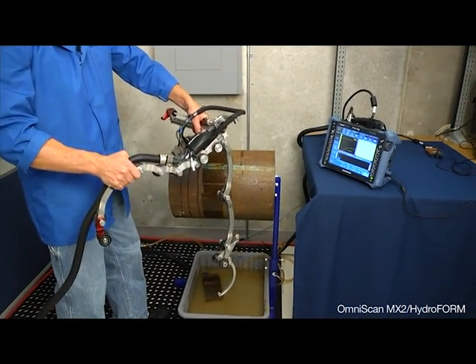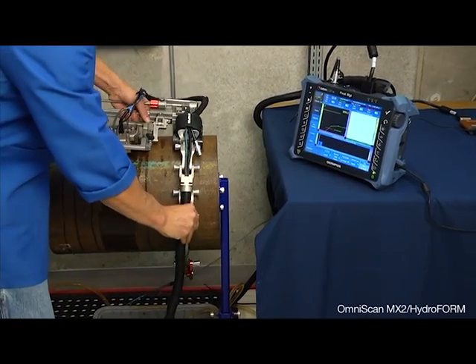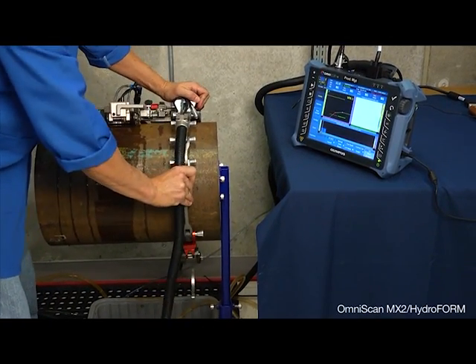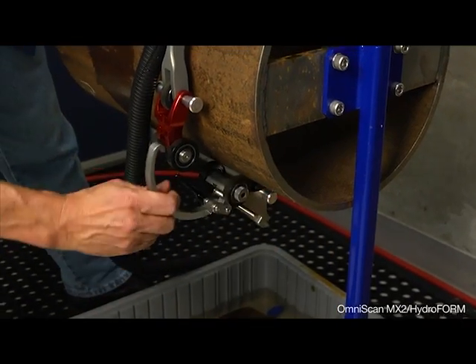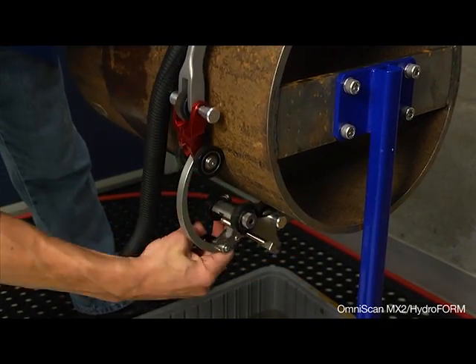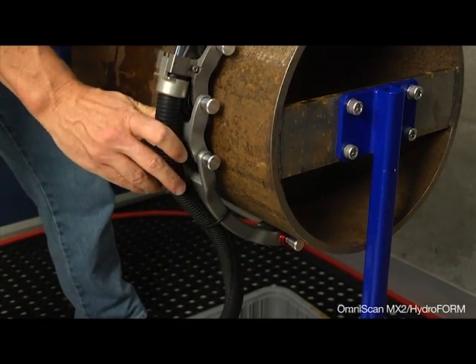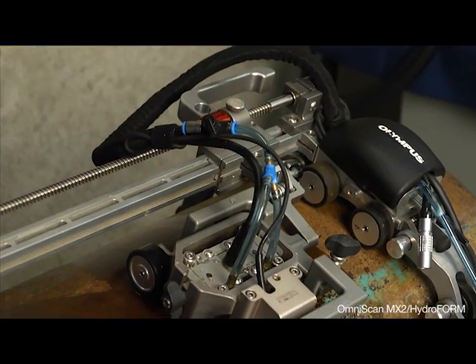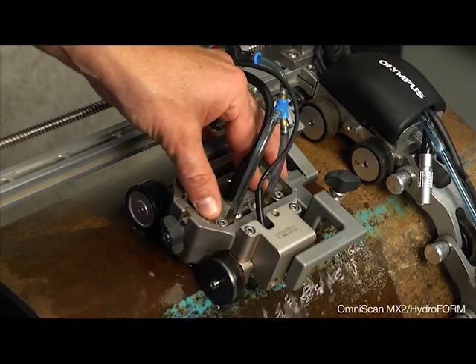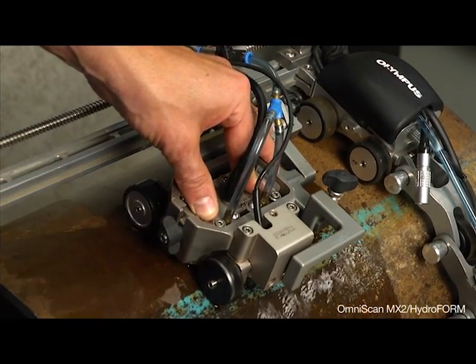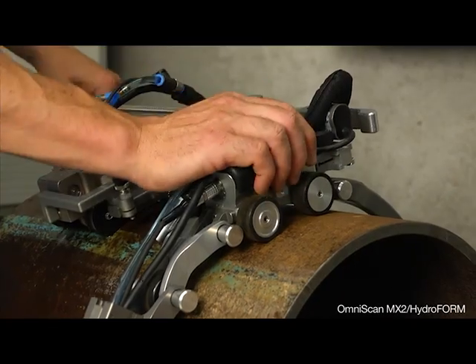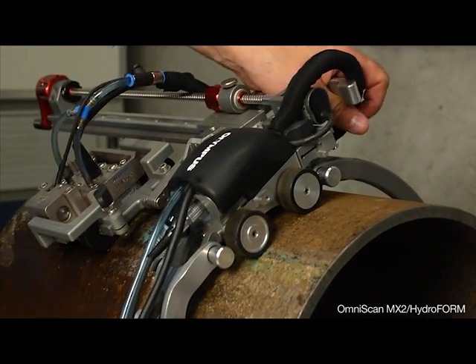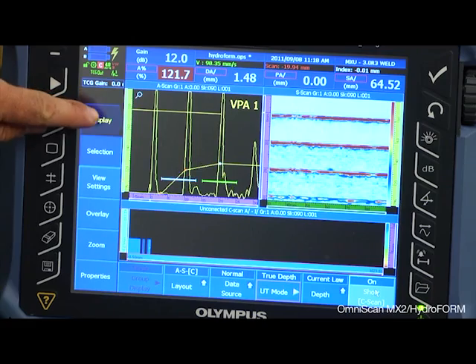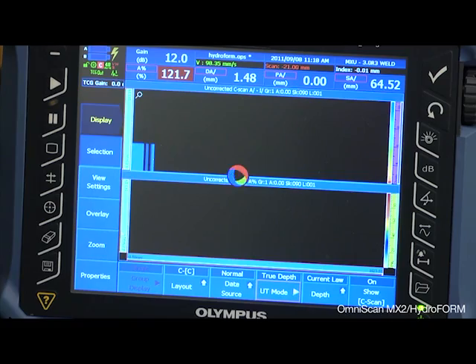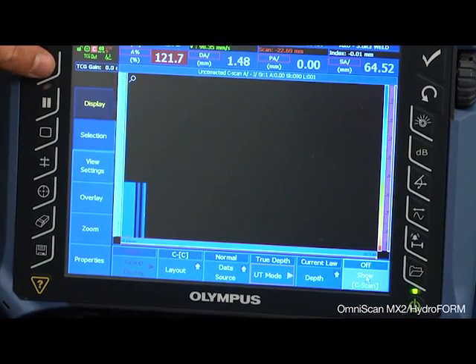Grab the chain scanner with 2 hands and place it around the circumference of the pipe, keeping it as parallel as possible to the pipe surface. Reach around with 1 hand and grab the hook and set it and clasp it tight. We'll flood the water column, we'll shake the scanner to ensure it's free of bubbles. We will use the C-scan layout for the inspection. Hit the Start Acquisition button that will reset the encoders, and we're ready to start acquiring data.